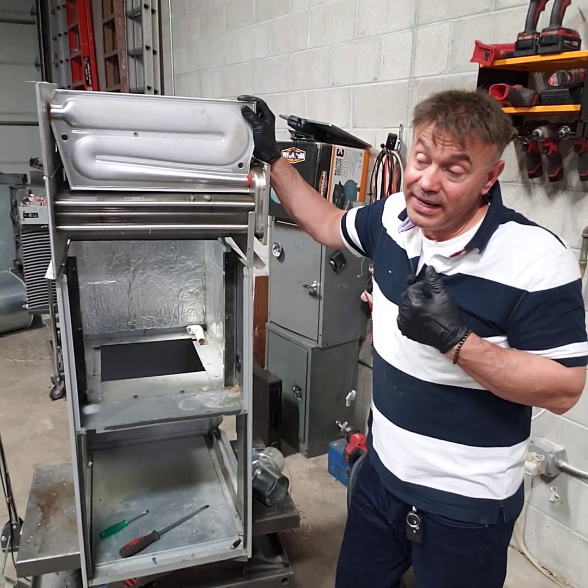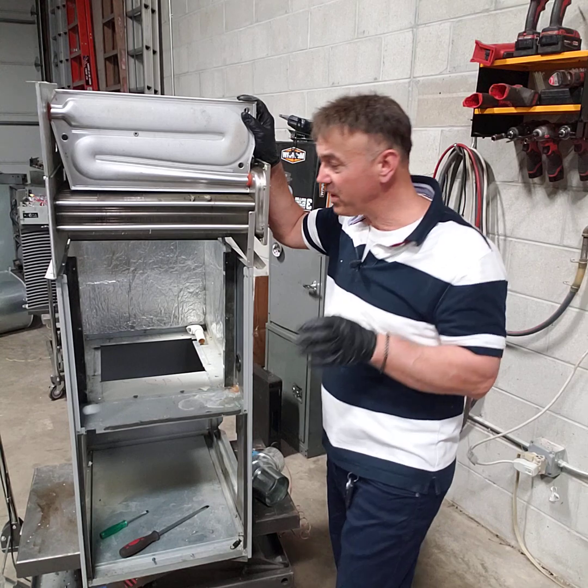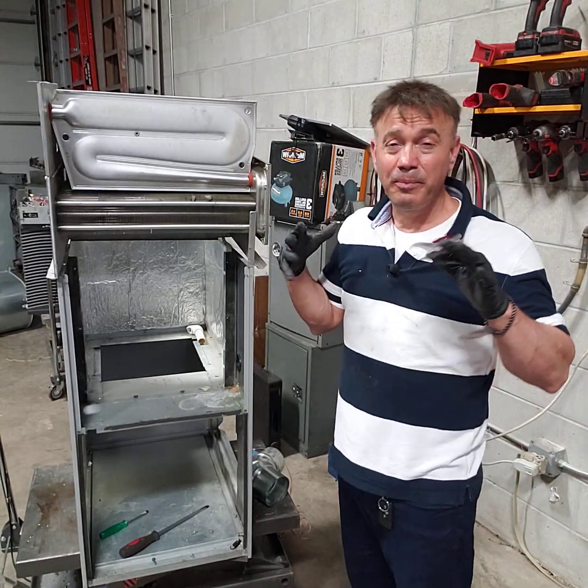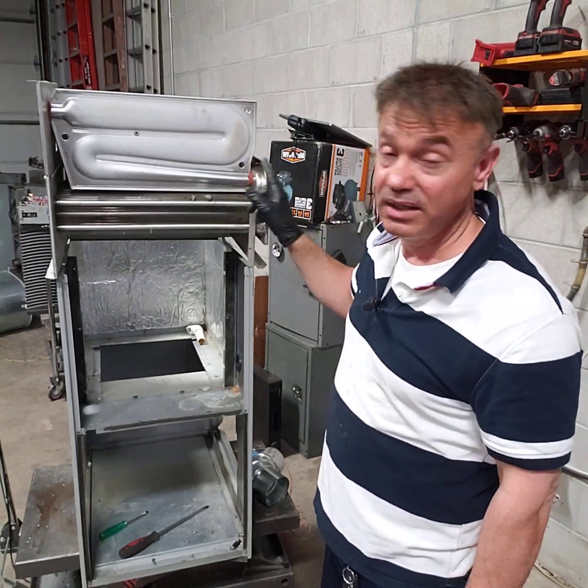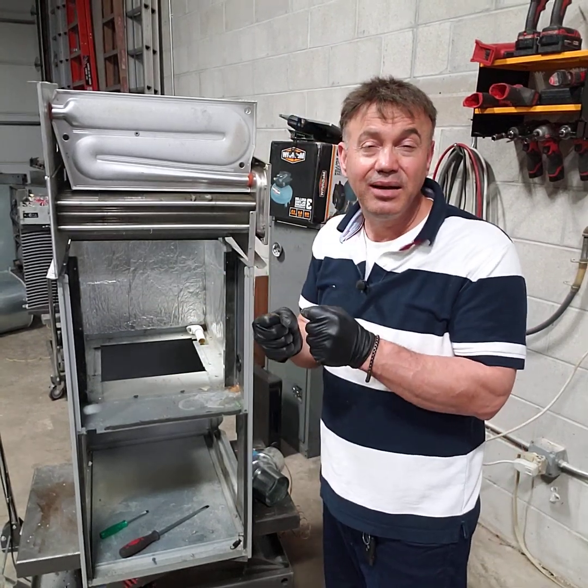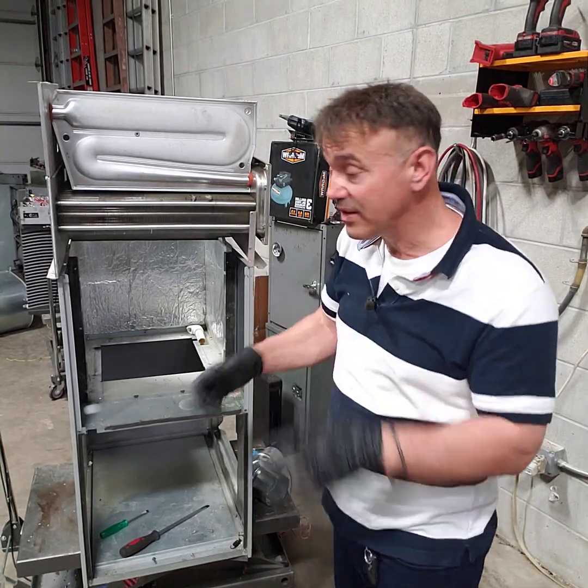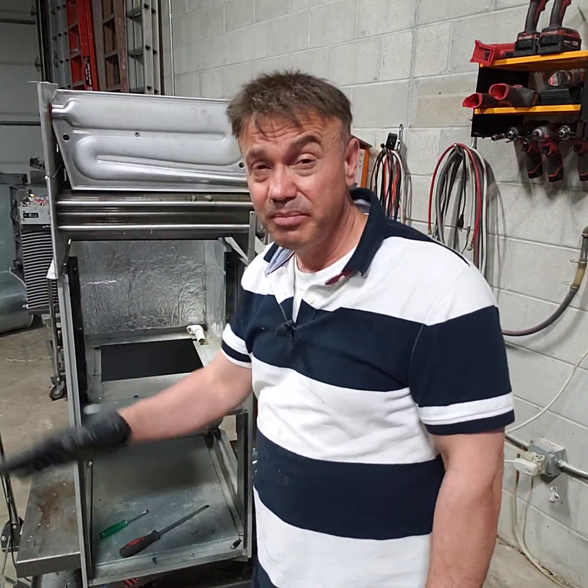Now again, forgive me guys, I might sound crazy. I don't recommend high efficiency furnaces. Honestly, they break so much, and you need a lot of maintenance, a lot of extra moving stuff, more wear and tear. Because again, remember, when that fire is coming in here, it's still dry. As soon as it goes into the high efficiency, the auxiliary or secondary heat exchanger, it will start becoming kind of vapor. It starts sweating. So there's a lot of sweating. And you remember earlier there was a condensation trap, because that condensation has to go somewhere, and usually it goes into the trap and it goes into your sump pump or condensate pump or into the drain.